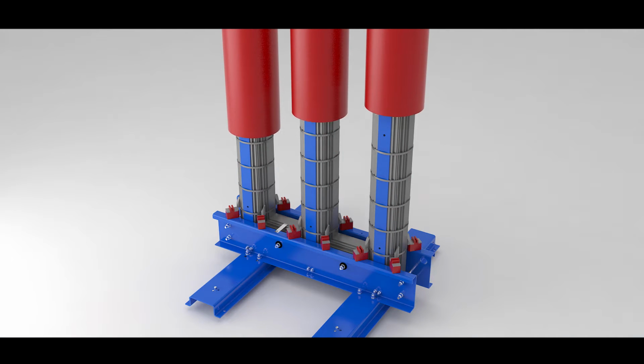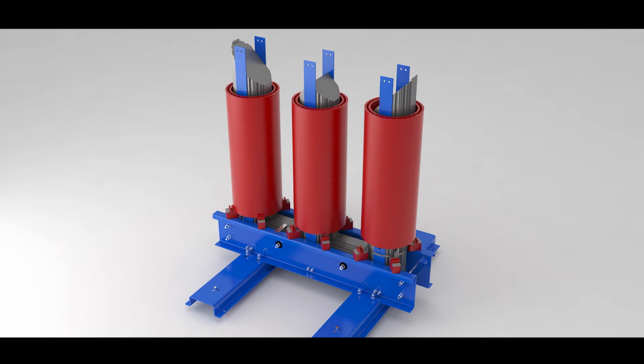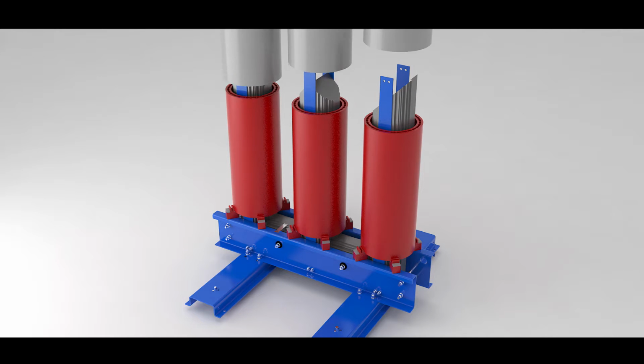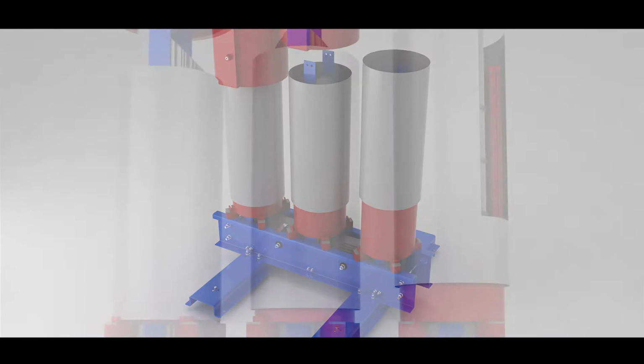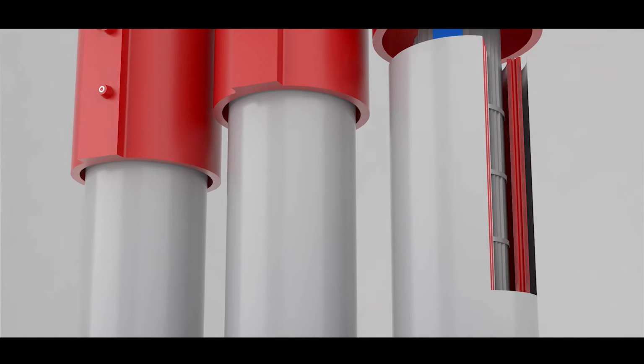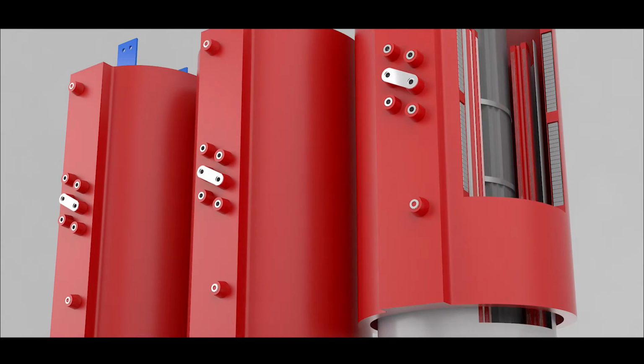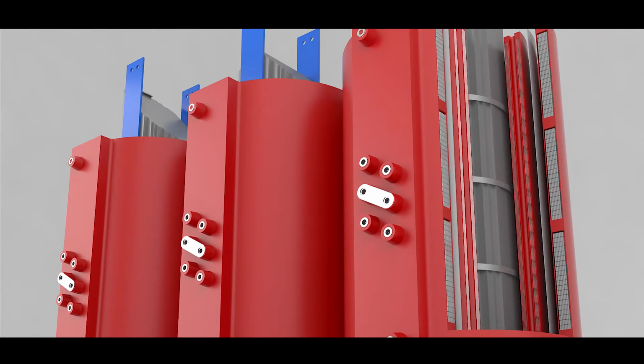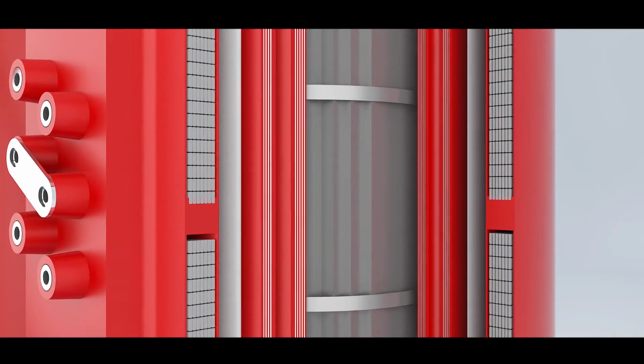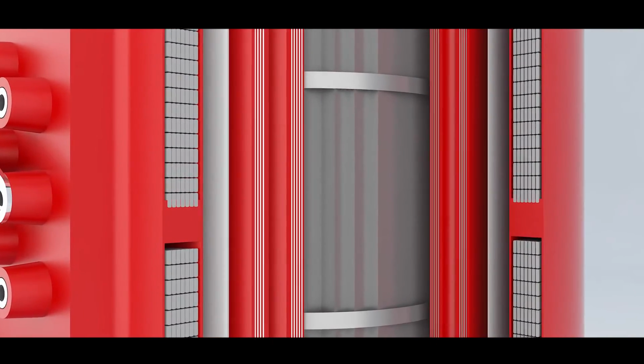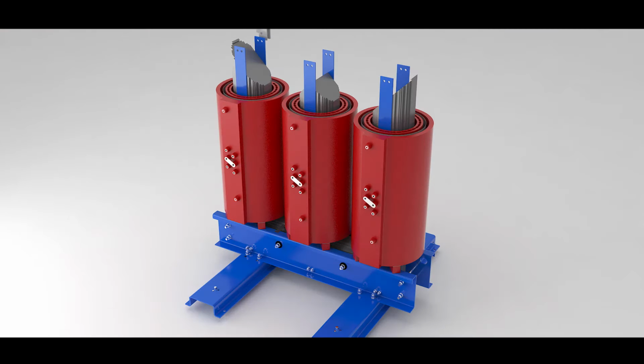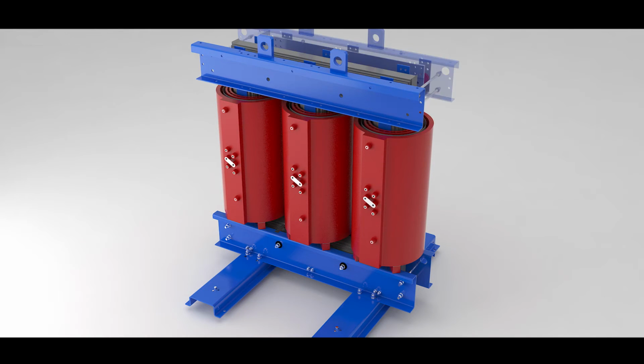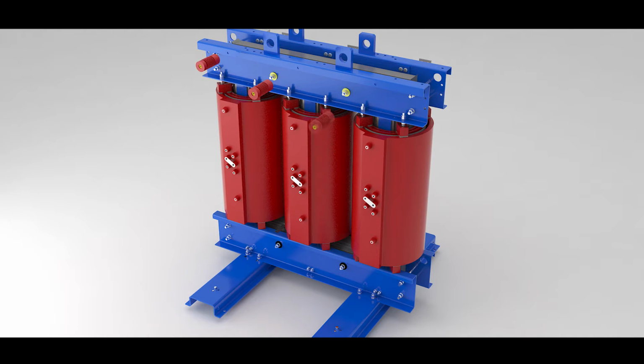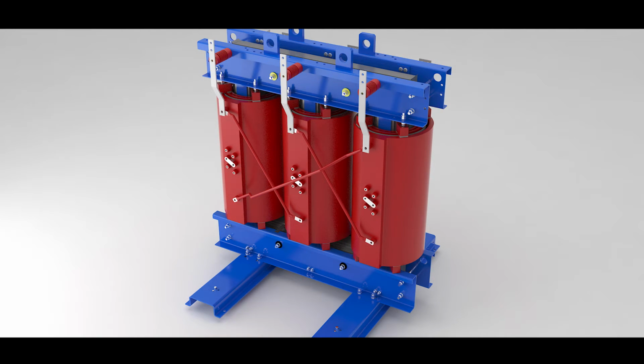Both our high voltage and low voltage coils are solidly cast in pure epoxy resin, and these windings are rigidly bound by a fiberglass mat to add unmatched strength. This construction ensures exceptional strength to guard against any short-circuit mechanical forces that are always possible. The voltage-withstanding strength of our insulation system can reach levels of up to 200,000 volts. Every part of the coil winding is protected against moisture or harsh environmental components to assure proper function, and therefore can be started up at a moment's notice without the usual pre-drying time needed for VPI construction.